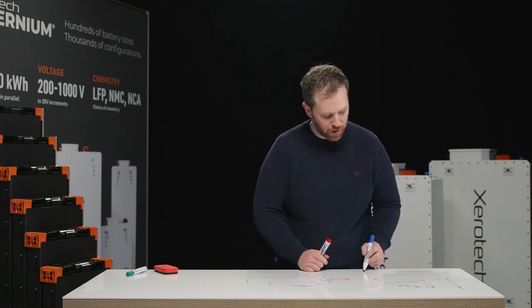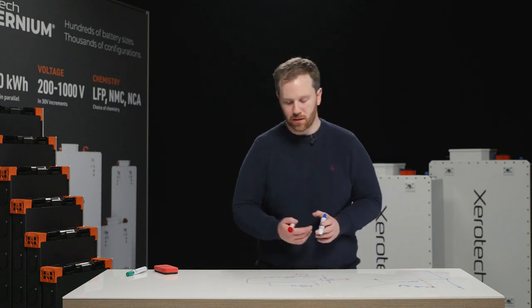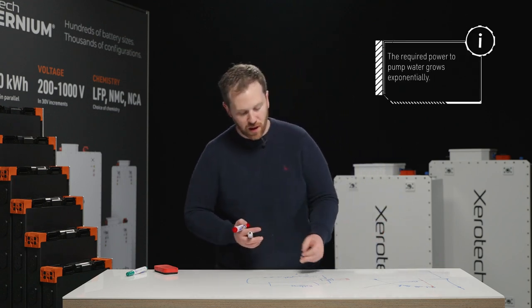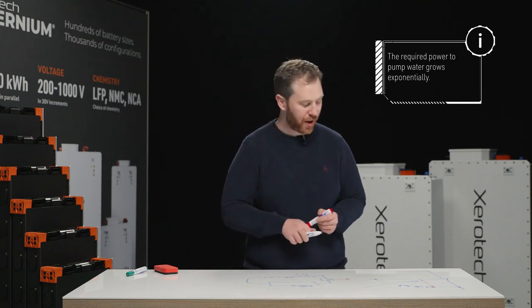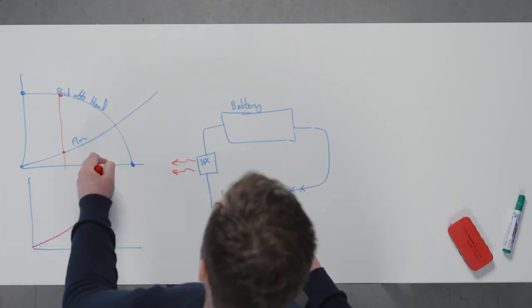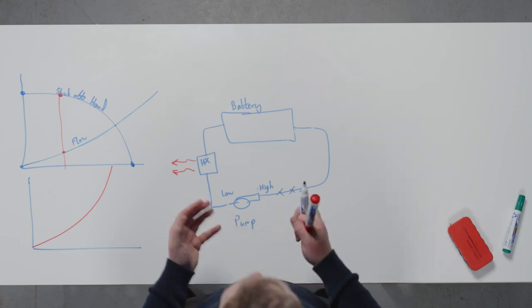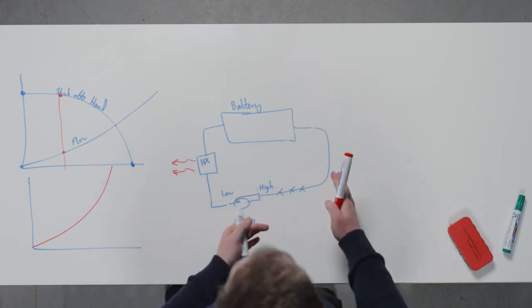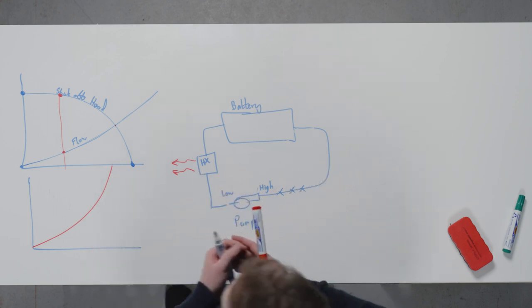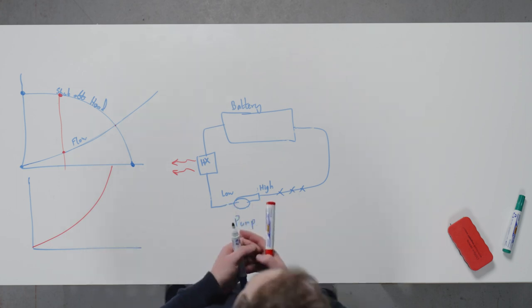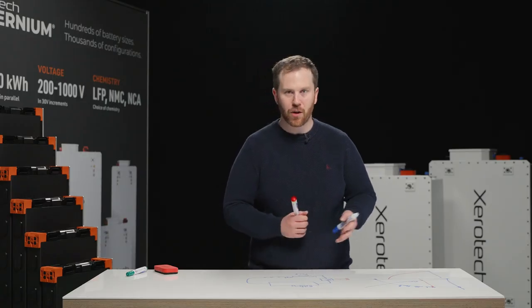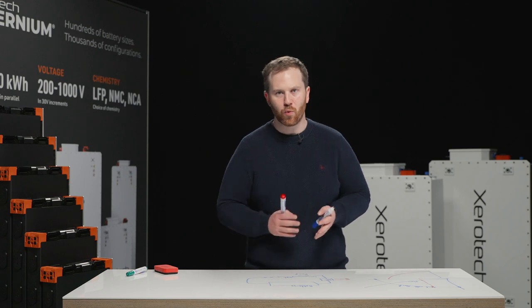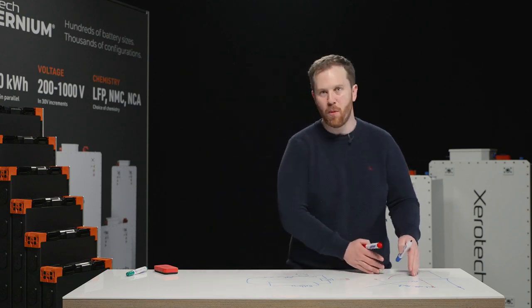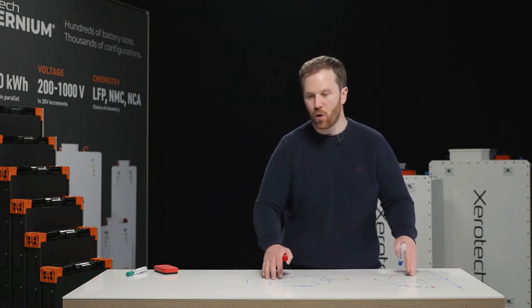The second important rule with pumps and pumping systems is that the power you need to pump through something is non-linear, it's actually exponential. So it's very hard to get a higher flow rate through a system if it's got a lot of constrictions in it. You can't just double the amount of pumping power you need in the system. It goes up exponentially. So it's really important that you've got a low pressure drop system. You don't want to have anything that obstructs the flow of water.